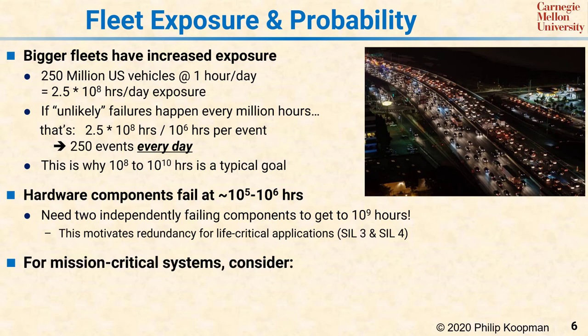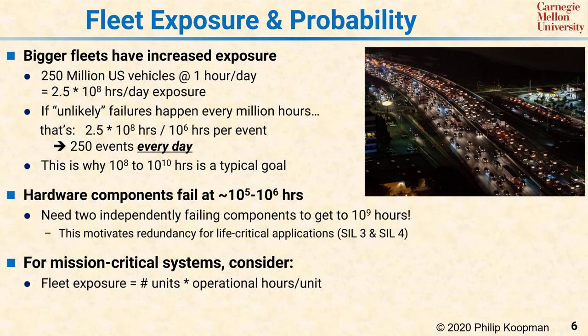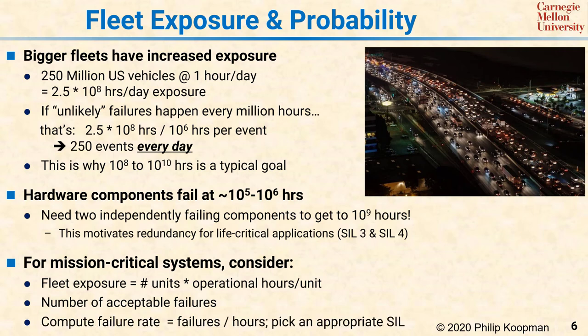If you have a mission-critical system and are not required to follow a safety standard, the approach is: first, determine the fleet exposure you expect — the number of units you're going to build times the number of hours an average unit will operate. Next, determine the number of acceptable failures at a particular level of severity, then compute the acceptable failure rate by dividing failures by hours. Use that number to look up in a reasonable safety standard what SIL should be achieved. For example, if you'd like your system to fail less often than every 10 million hours, you might adopt IEC 61508 SIL 3 — not because you're life-critical, but because that standard targets a residual failure rate of about 10^7 hours, which is your target number.